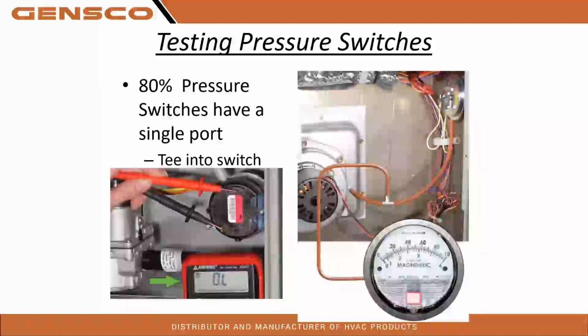So testing pressure switches, 80% are going to have a single port. They are open burner, so you do not have to reference the open burner. So we want to tee in, excuse me, and check the position. Before the unit turns on, we're going to see if we have a closed switch or an open switch. Then we're simply going to tee into it. We want to tee into it and see it actually live, okay?